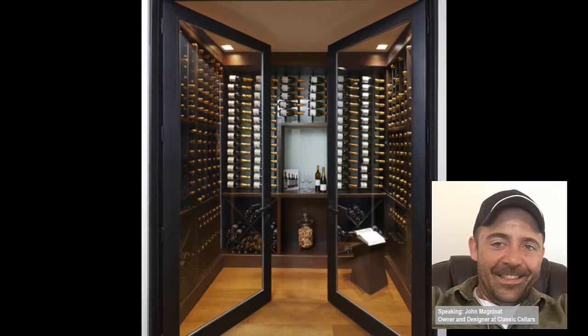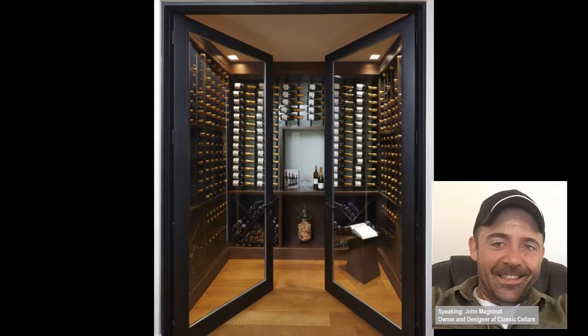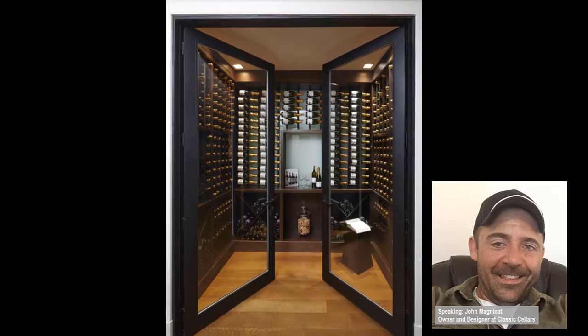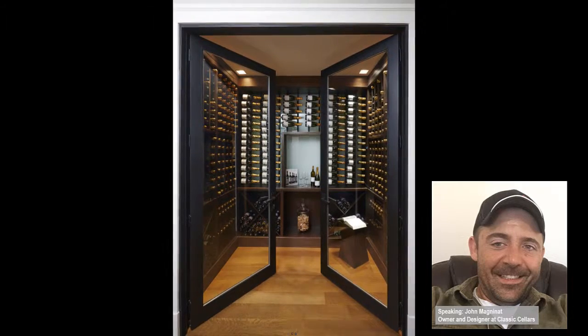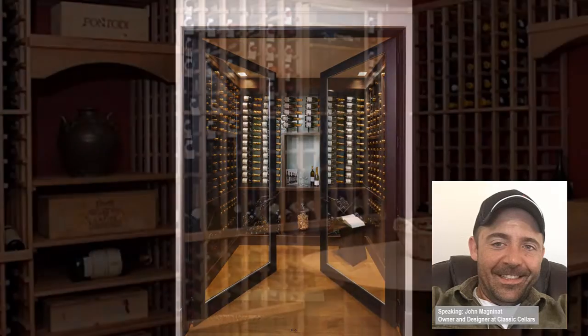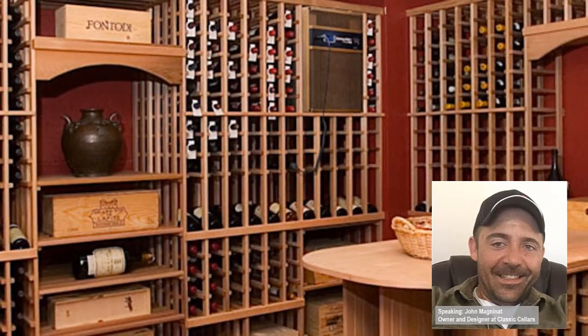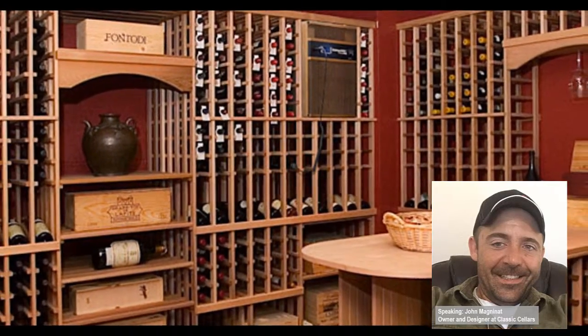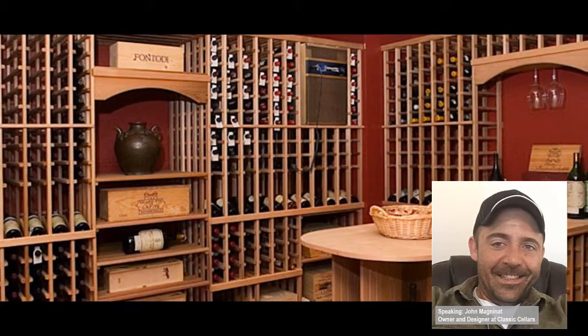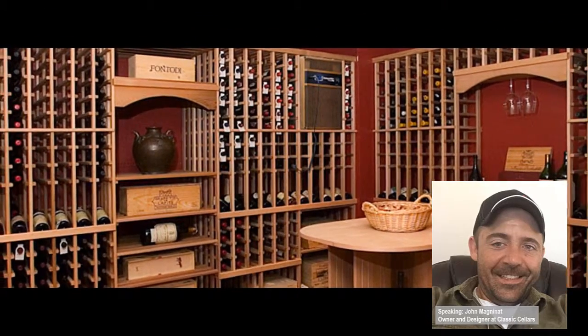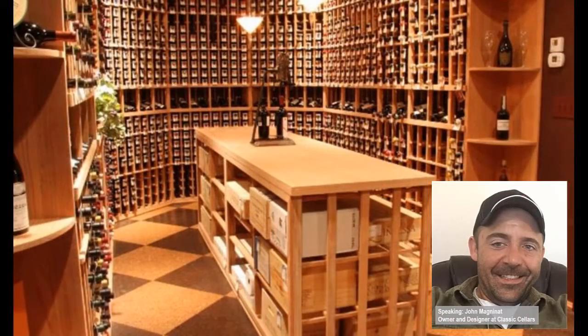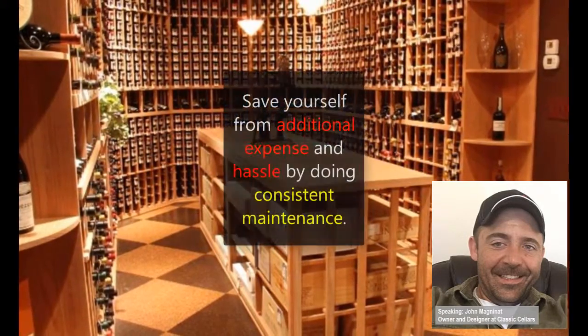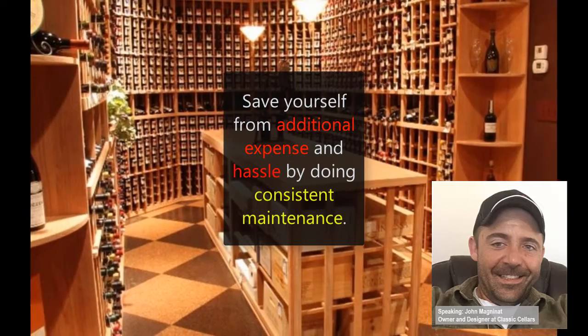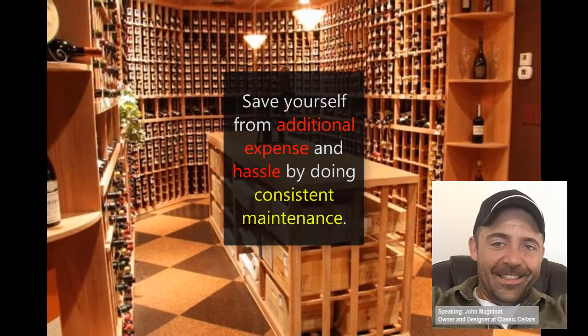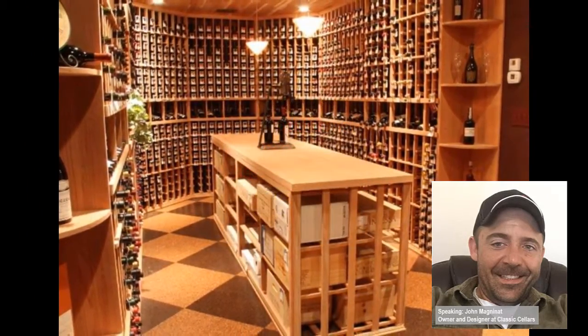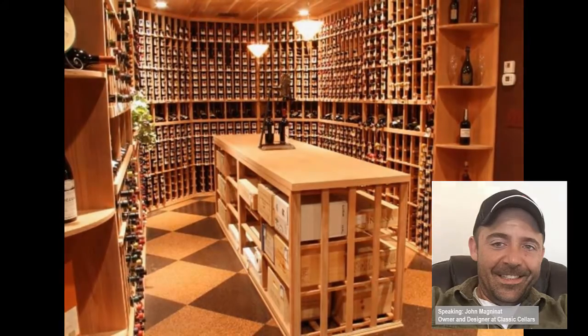Or it really kills me, we see it probably once or twice a year, a capacitor will fail on a compressor, and the homeowner will just leave it on. Without that capacitor in place, it will burn that compressor up. So now we've taken a couple-of-hundred-dollar, real simple repair for a capacitor, and now it's a several-thousand-dollar repair. Odds are, if they'd had preventative maintenance done, they could have caught that and saved themselves a lot of money. I see it happen, so I'm definitely a fan of preventative maintenance.